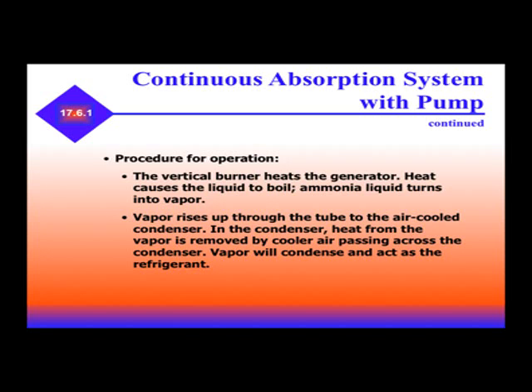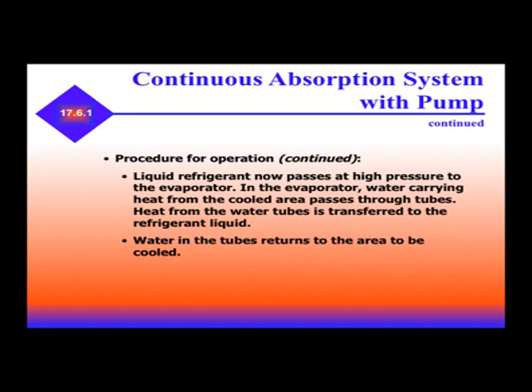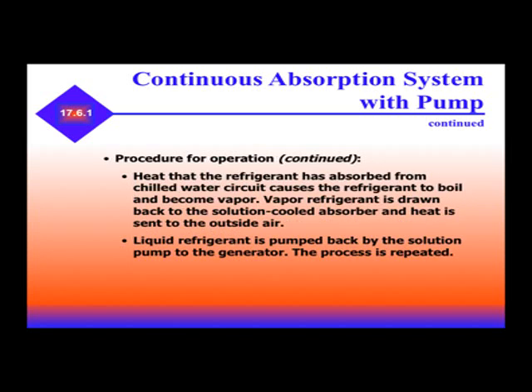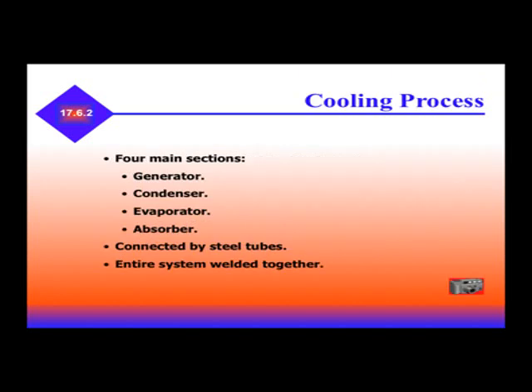With a pump, the sequence of operation is slightly different. The vertical burner heats the generator. Heat causes the liquid to boil and ammonia liquid turns into vapor. Vapor rises through the tube to the air-cooled condenser, where heat from the vapor is removed by cooler air passing across the condenser and the vapor condenses as a refrigerant. Liquid refrigerant passes at high pressure to the evaporator, where water carrying heat from the cooled area passes through tubes and transfers heat to the refrigerant liquid. The refrigerant boils and becomes vapor, is drawn back to the solution in the cooled absorber, and heat is sent to the outside air. Liquid refrigerant is pumped back by the solution pump to the generator and the process is repeated.